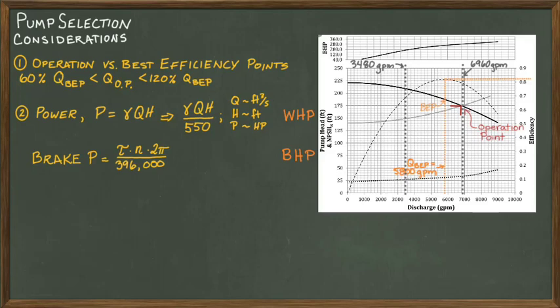There are losses as power is transferred from the shaft to the impeller and to the fluid. So the pump efficiency, which is sometimes written with the Greek letter eta or the Roman letter E, is simply the ratio of the water horsepower divided by the brake horsepower.